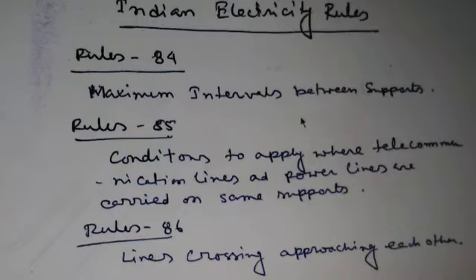All conductors shall be attached to supports at intervals not crossing the safe limit, based on the ultimate tensile strength of the conductor and the factor of safety. And this rule is related to rule number 76, provided that in the case of overhead lines carrying low or medium voltage conductors, when crossing over, along and across the street, the interval shall not be exceeded without the consent in writing of the inspector.